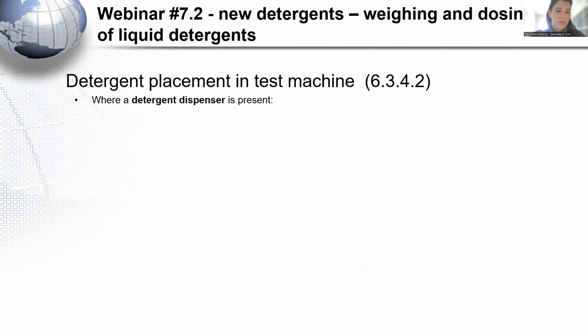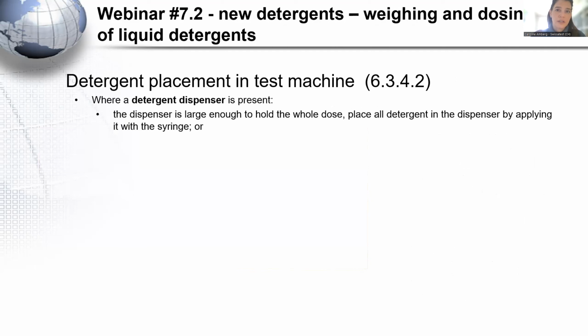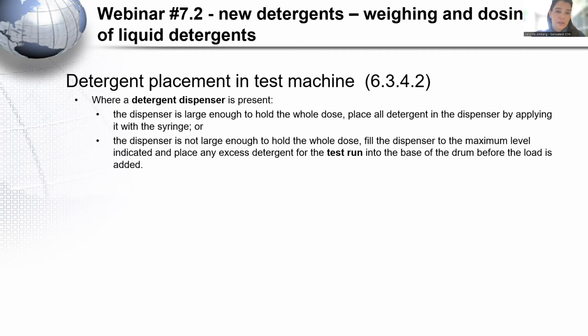Yes, and then another point is not only the weighing, we also have to apply the detergent to the machine. This is relatively easy when a detergent dispenser is present in a test machine, and when this one is large enough, then it's just applied to this dispenser with the syringe, for example, or with this pipette. When the dispenser is not large enough, then it is filled up to the maximum level, and the rest of the detergent is placed in the drum, so in the base of the drum, before you load the machine.